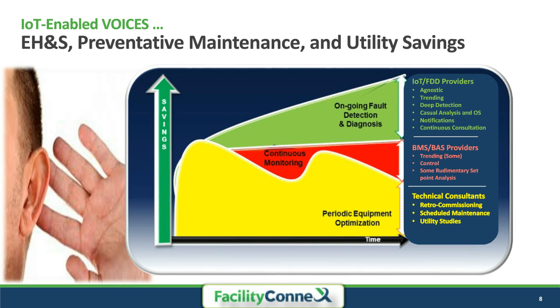Commissioning tends to happen sometimes on a 5 to 10 year basis. During that time, equipment actually drifts over time. It starts to degrade, things get changed, people make simple measurement changes, new equipment is added, and there's no sense of balance or recommissioning that typically occurs. So you get this drifting effect, but over time it really impacts the cost of running that equipment moving forward.